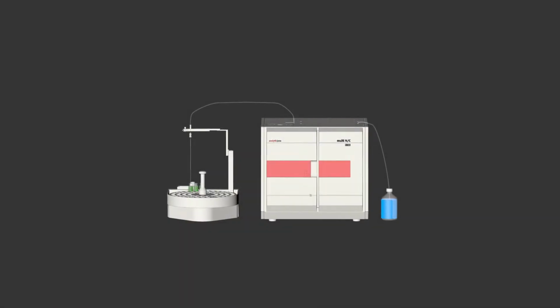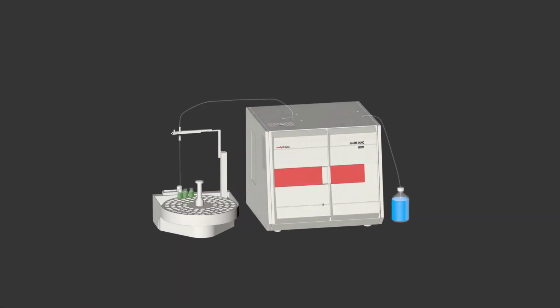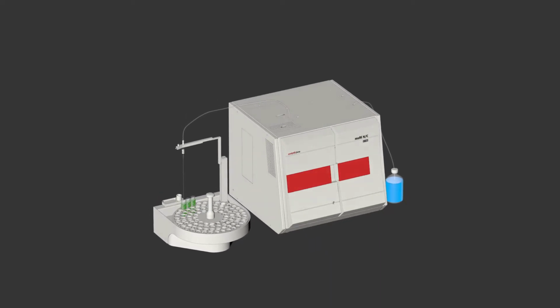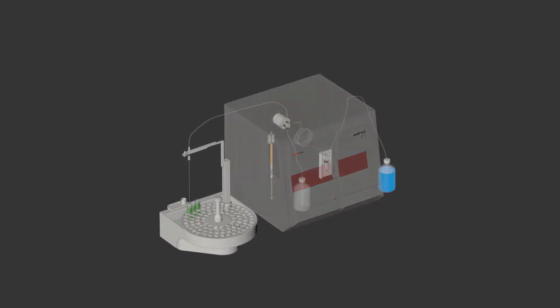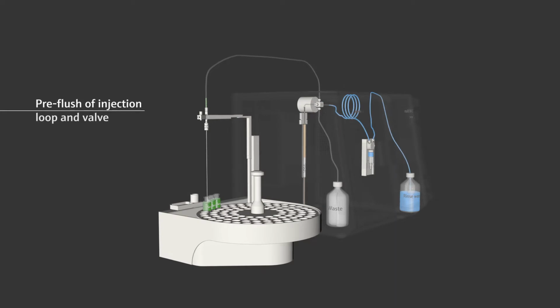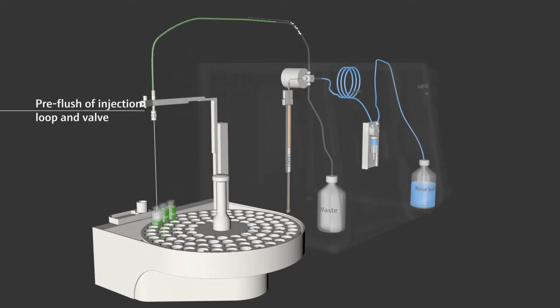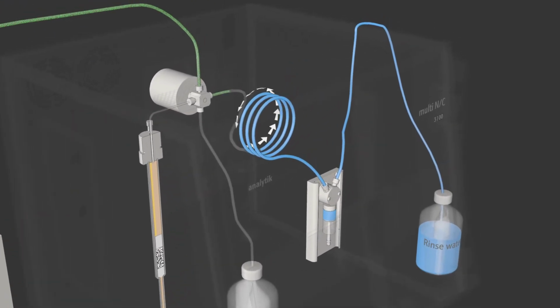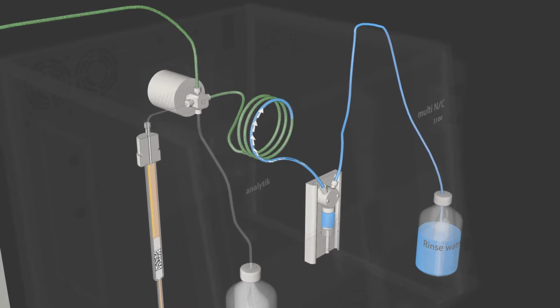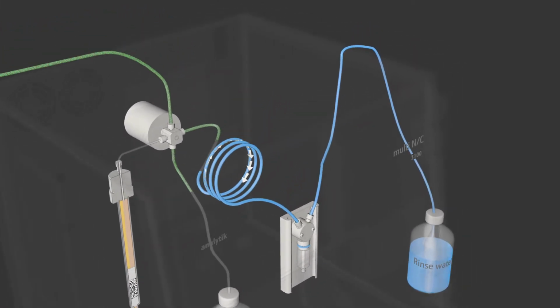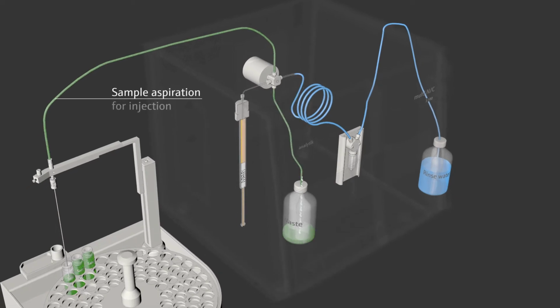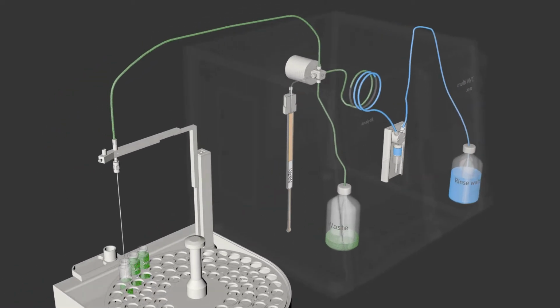Analytik Jena's unique flow injection technique guarantees reliable results. The MultiNC 3100's large diameter tubes provide superior particle handling capabilities. When the sample is taken into the injection loop, no sample and particles enter the syringe pump. This minimizes, together with an effective rinse, carryover and material wear.